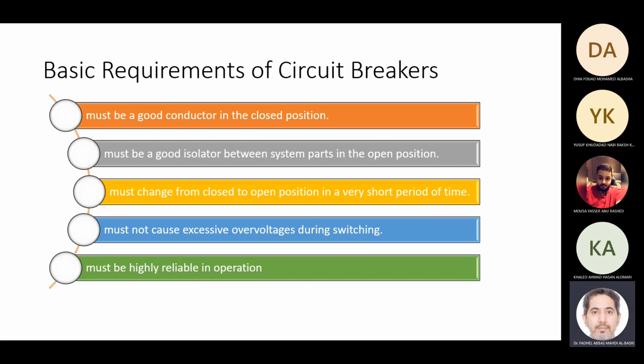There are basic requirements for a breaker. When it is in a closed position, it should act as a zero resistance. When it is in open position, it should be like an insulator. It should open in a very short time, and close also in a very short time. It must be reliable, and it should withstand and not cause an overvoltage during switching.